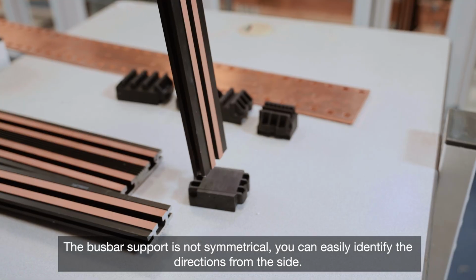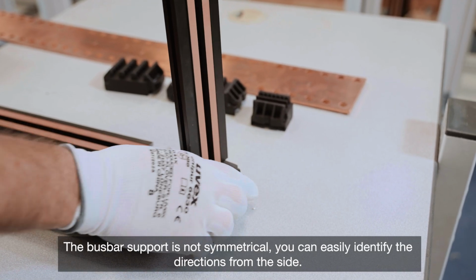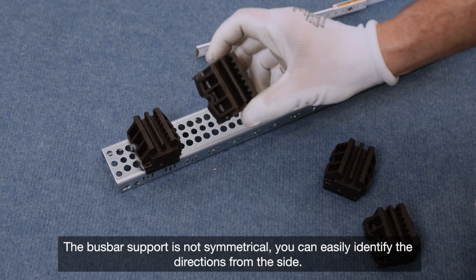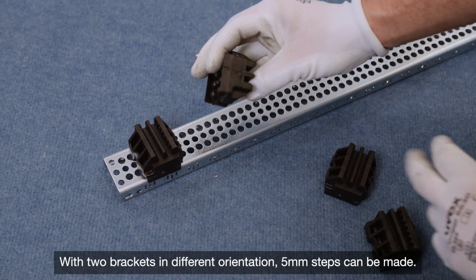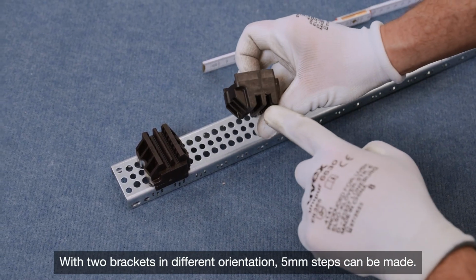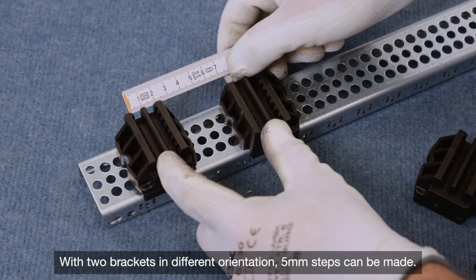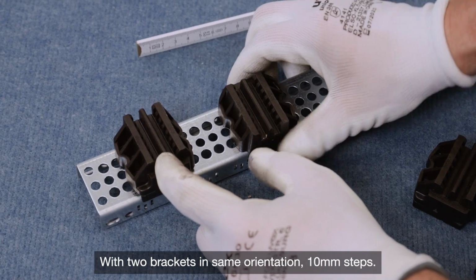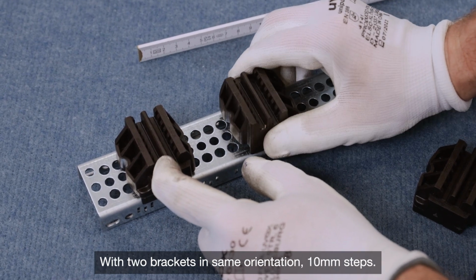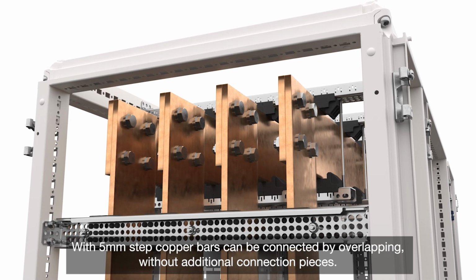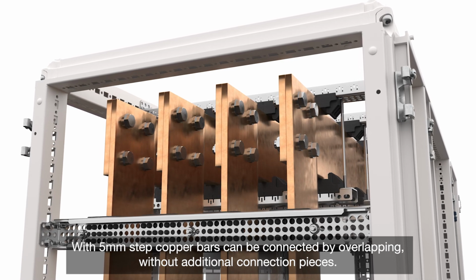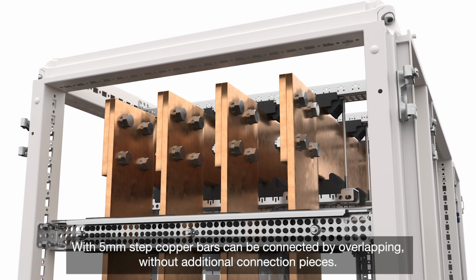The busbar support is not symmetrical. You can easily identify the directions from the side. With 2 brackets in different orientation, 5 mm steps can be made. With 2 brackets in the same orientation, 10 mm steps. With a 5 mm step, copper bars can be connected by overlapping, without additional connection pieces.